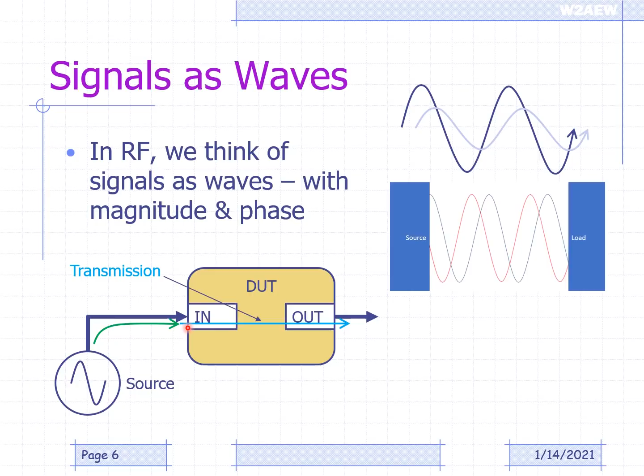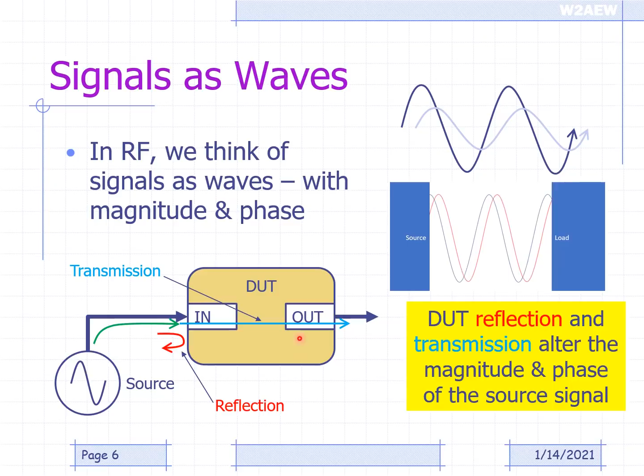So we can see it may be important to know what the phase is because that will vary depending on the transmission line length between a source and a load. So when we think about waves, we may have a wave that's being produced by a source going into a DUT. Any of that signal that goes through the device is called the transmission properties of that device. And any part of that signal that gets reflected off that interface due to an impedance mismatch is called the reflection properties of the device. Now the device reflection and transmission will alter both the magnitude and phase of the source signal. And a VNA measures the magnitude and phase of these reflection and transmission properties of a device.